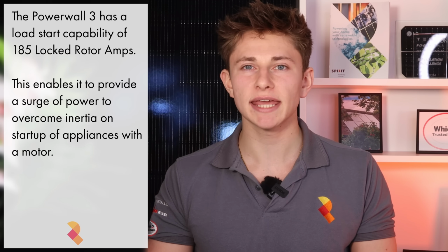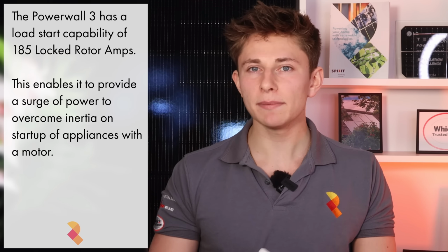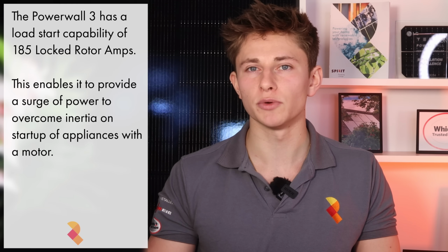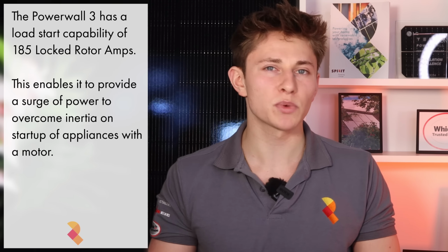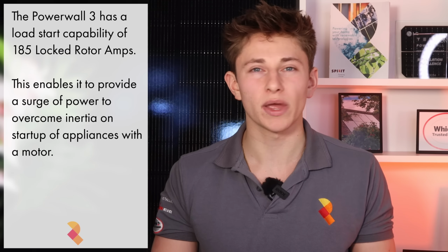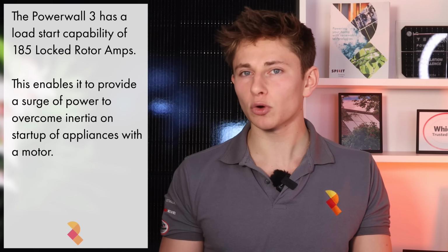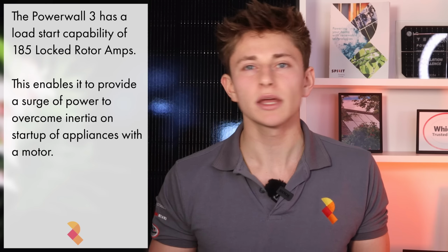The Powerwall 3 inverter does have a peak power output of up to 185 locked rotor amps, enabling it to provide a surge of power to support load startups. When an appliance with a motor, like a fridge, aircon or heat pump, switches on, it needs a quick surge of power to overcome inertia and get the motor spinning. During those first few milliseconds, the motor behaves like a short circuit, drawing a very large current, often 5 to 8 times higher than its normal running current. Powerwall 3 can support this by outputting up to 185 amps for a brief time period.